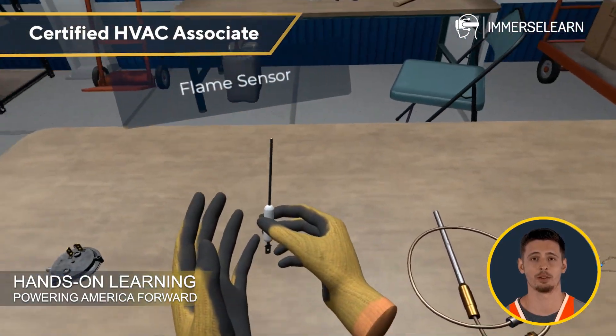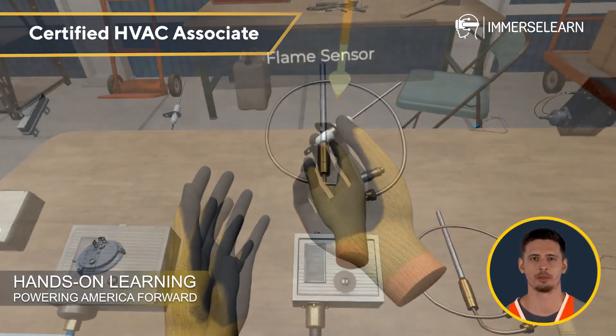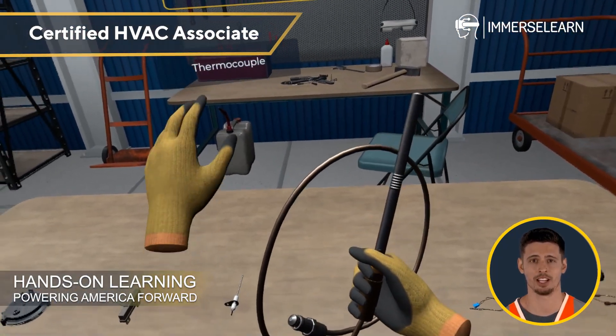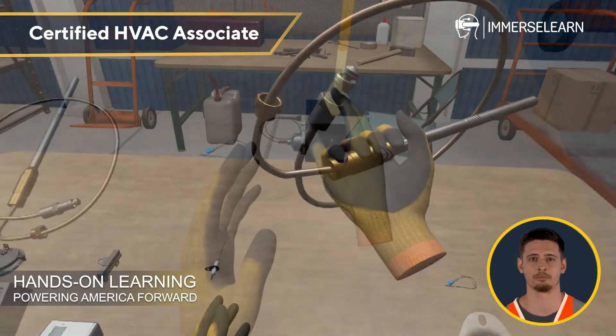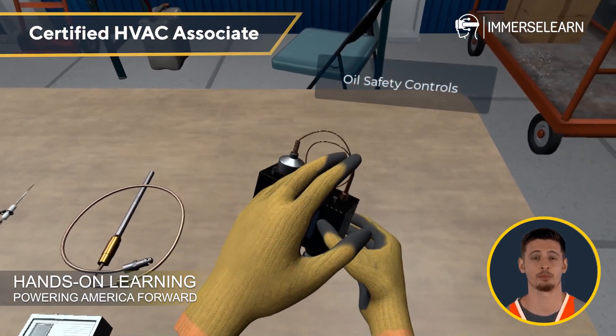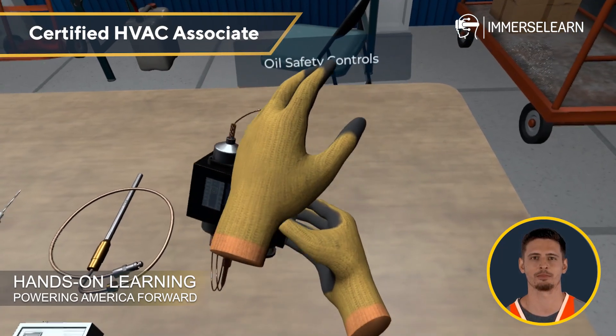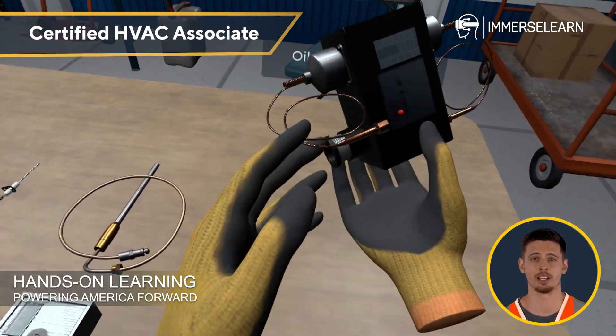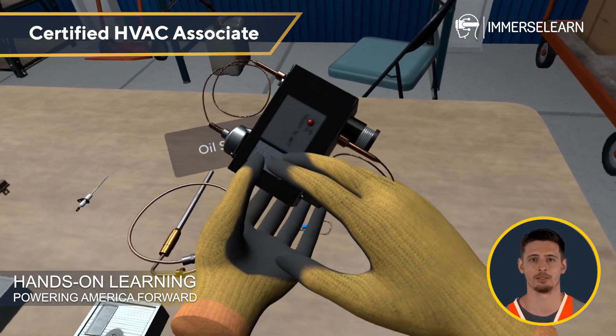Flame sensors and thermocouples detect and confirm the presence of a flame, making them crucial for system reliability. Inspecting them for dirt or damage ensures accurate performance. Finally, let's look at oil safety controls. These monitor oil pressure and keep operations running safely. By checking their function, secure connections and cleanliness, you'll ensure smooth and safe HVAC performance.